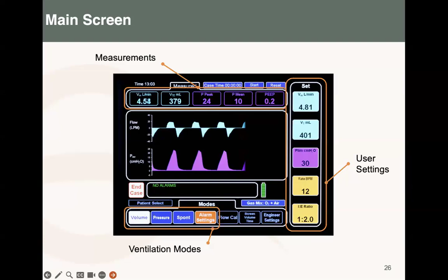For example, if I set the volume at 400, and the machine gives maybe 200, and maybe there's another alarm, that will give me a clue. Maybe there's a leakage somewhere. So instead of just jumping to the alarm and panicking, always compare the set values and the measured ones, and from there that will give you a clue what should be looked at next. Next.